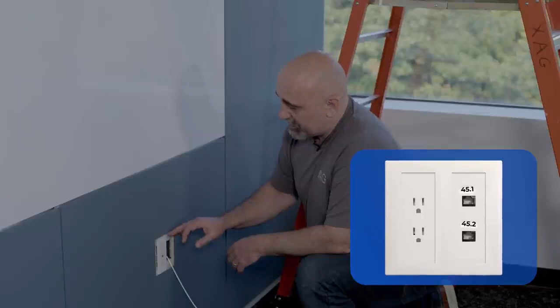This is a unique install. These electrical boxes are specifically designed to be able to have electrical and data in them. That is not typical—it is specifically designed to support that. Normally you would find your electrical in one box, and then you would put your data next to that. If they weren't in conduit, make sure that you're maintaining your distance between your electrical run and your data run.